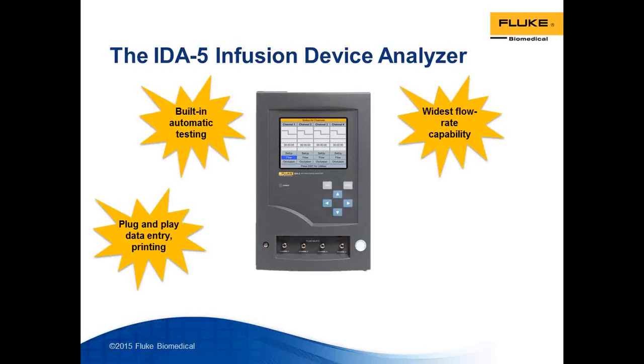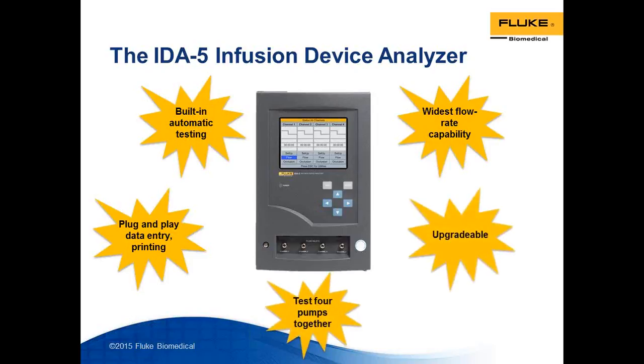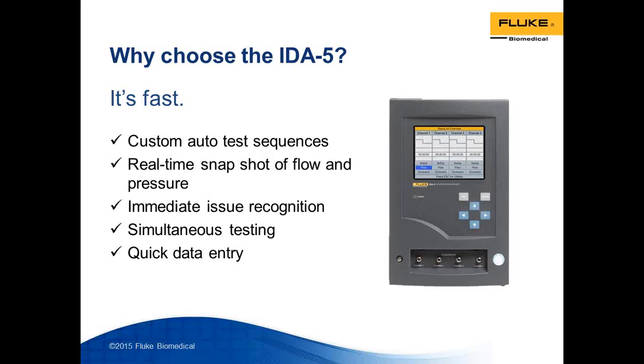But essentially, it's 1,500 milliliters per hour, up to 2,600 milliliters per hour displayed. It can test up to 4 pumps together, and it's upgradable, which means that although here we've got a 4-channel analyzer featured, you can add 1 or 2 or 3 channels at your convenience. So you can just buy a 1-channel or a 2-channel format and upgrade to suit your organization's needs. So the IDA-5 is very powerful in terms of its functionality, but also in terms of the fact that it packs a lot of capability into one analyzer.